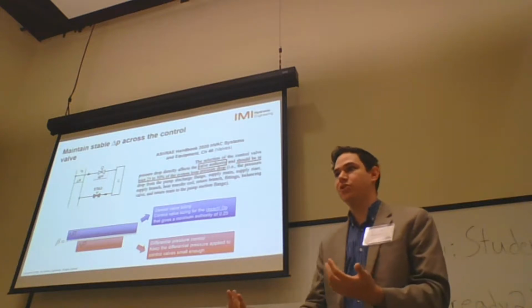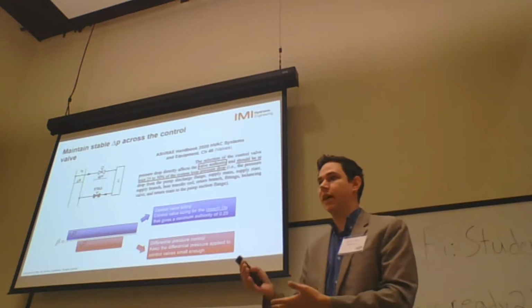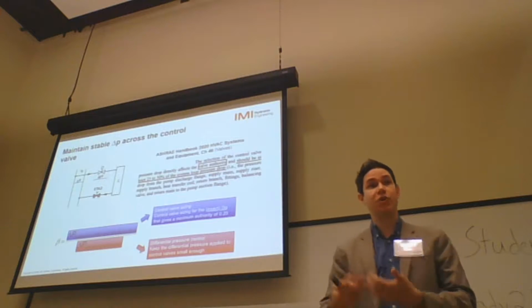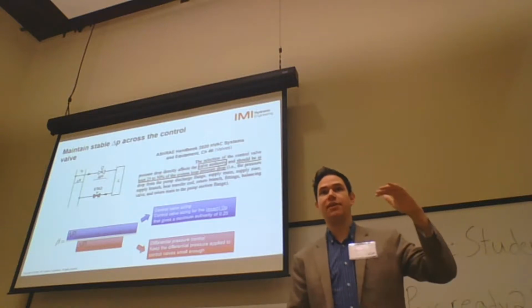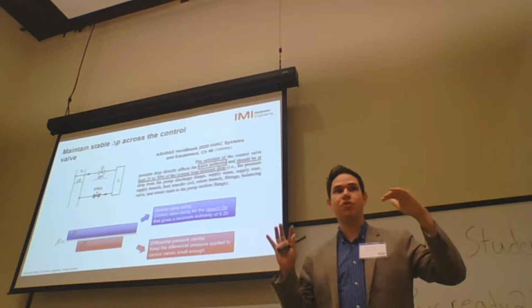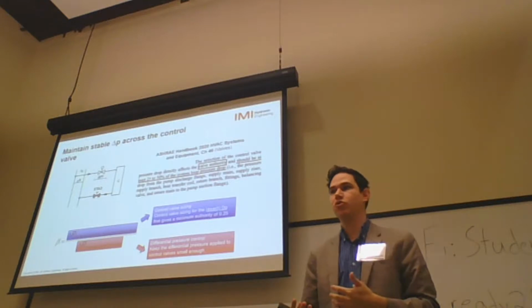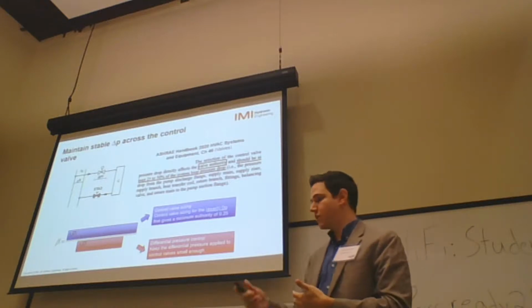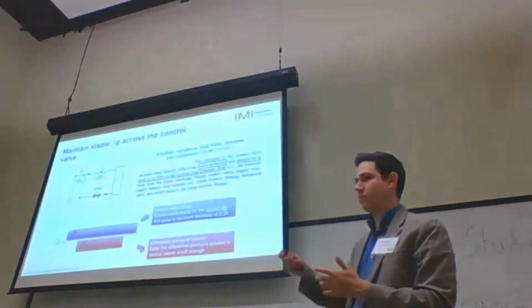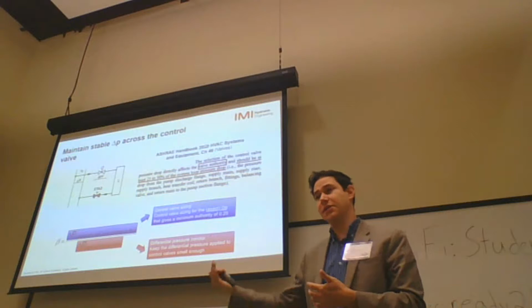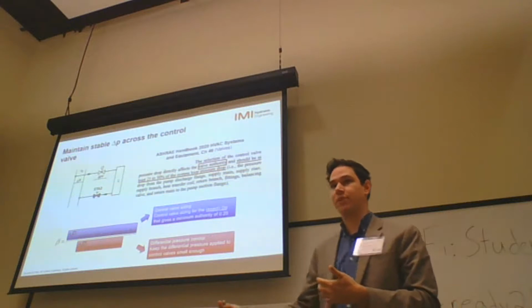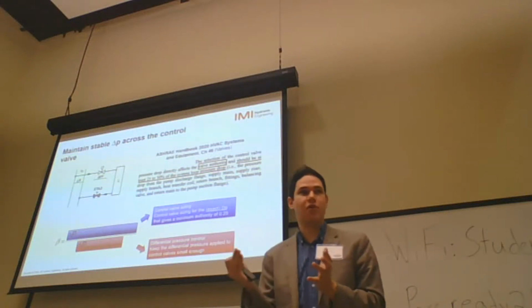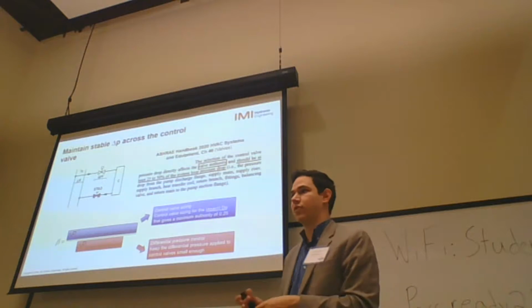The only thing we can do at the job site to help fix hunting in a control valve is to reduce the pump head. If I have less pressure going to the control valve, you help the control valve authority. If you look at the ASHRAE Handbook 2020, chapter 46, it discusses control valve authority a lot. In simple words, control valve authority is the sensibility of the control valve.